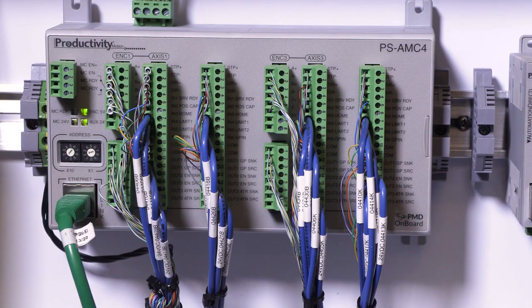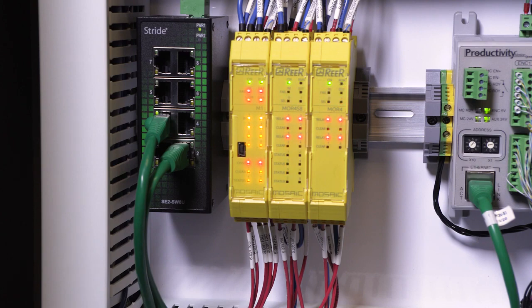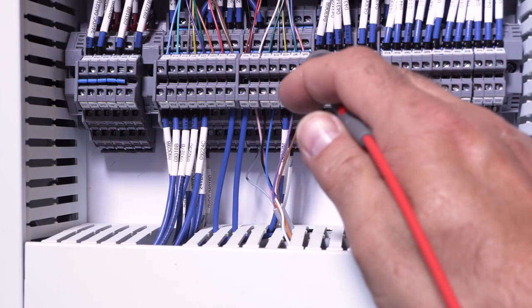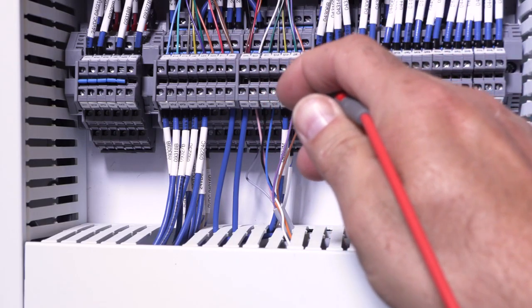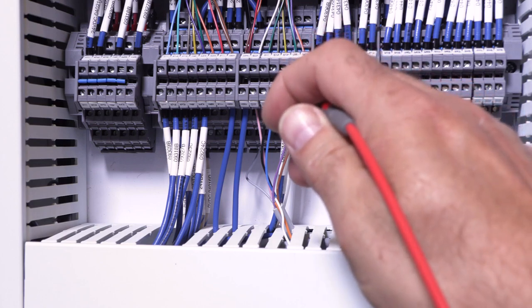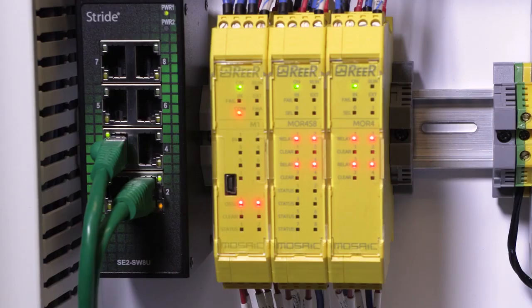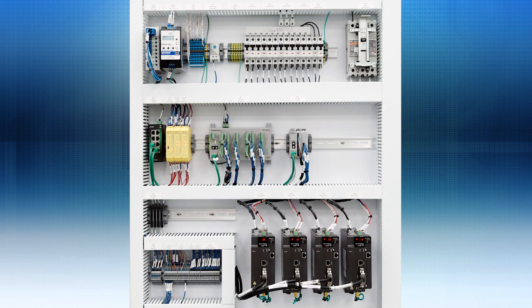Turn on the DC components one at a time, making sure the expected device turns on and that nothing powers up unexpectedly. Check for power where you expect it. For example, the power rail of I/O terminal blocks or the input side of a safety relay. Leave all your DC components powered for the remainder of testing. If everything checks out, it's time to move to I/O testing.